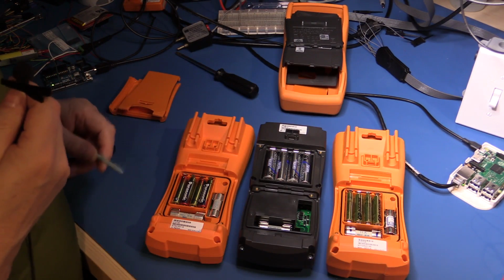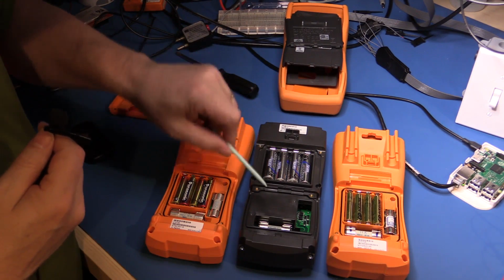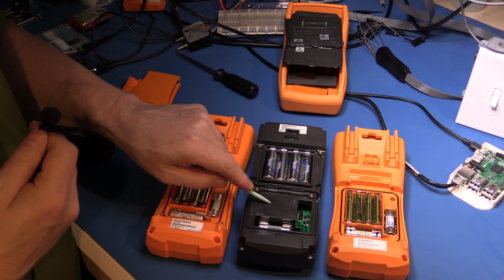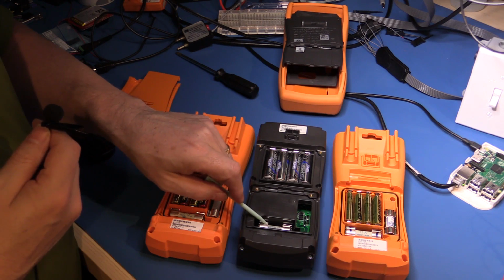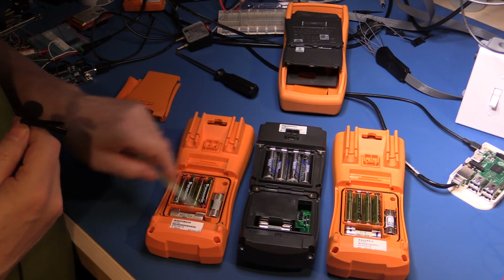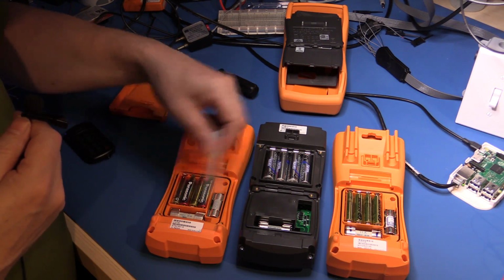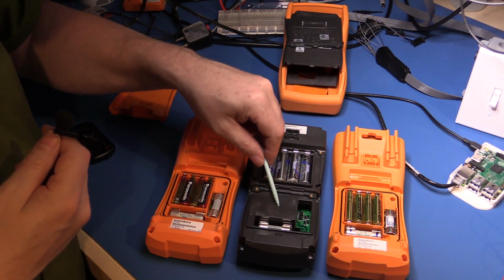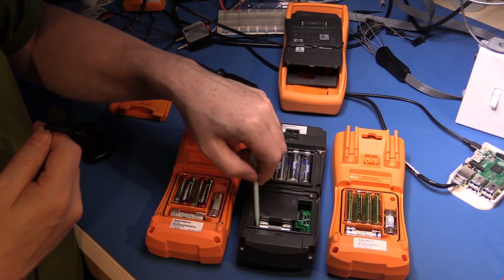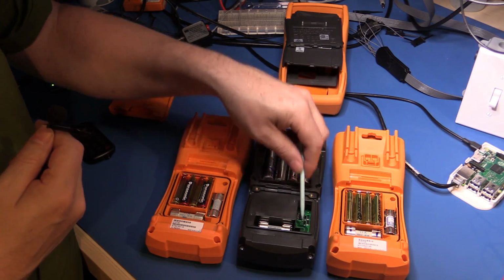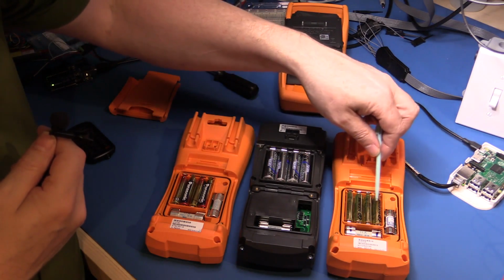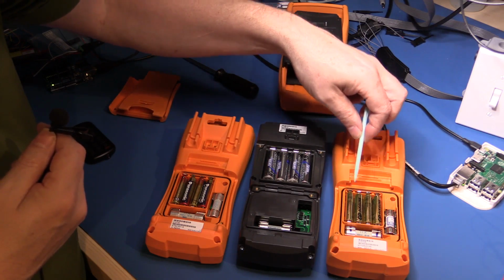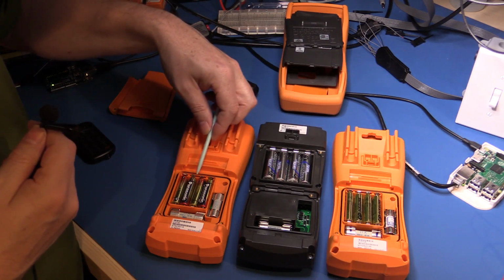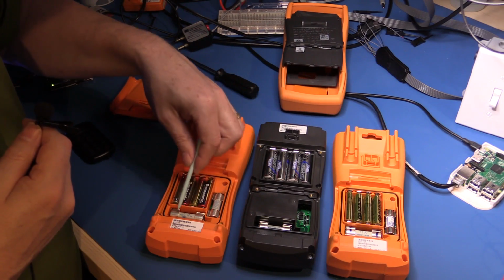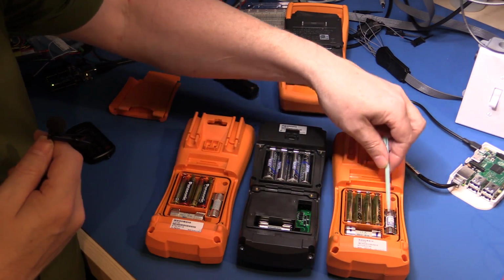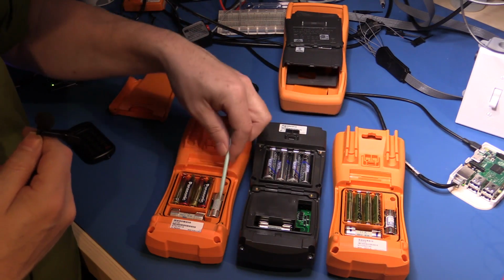So here's the first notable difference between the 2 meters. You can see this one, which is the 1461, only has 1 fuse, whereas these other 2 actually have 2 fuses in the battery compartment. And the layout is slightly different. On the 1461, the low amperage fuse is in the bottom compartment here, and the one on the side is left empty, whereas on the 1172A and the 1173A, the high current fuse, it's 11 amps, is on the bottom, and the smaller 450 milliamp fuse is up the side here.